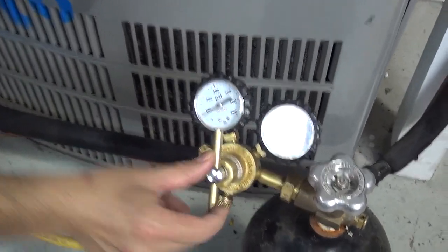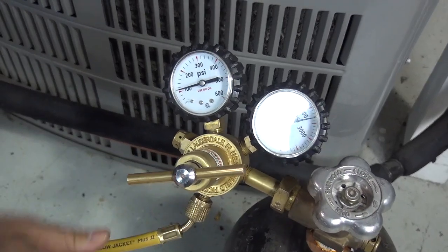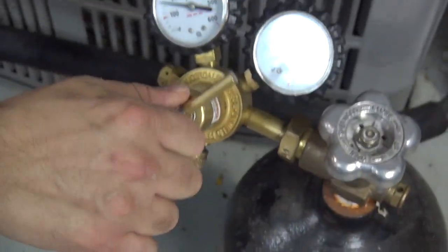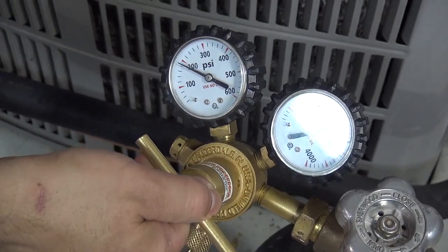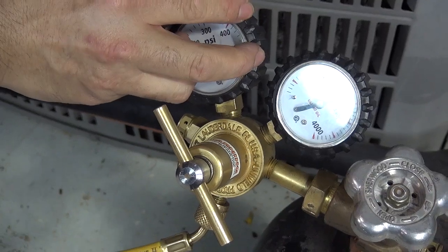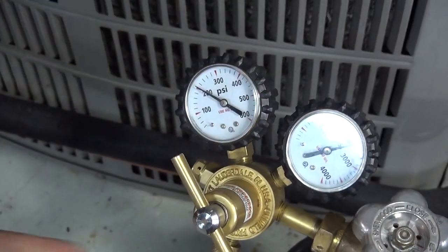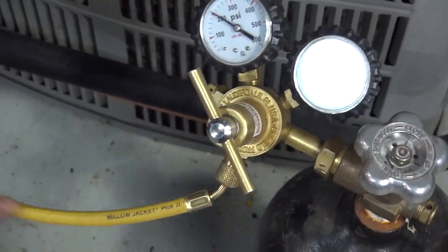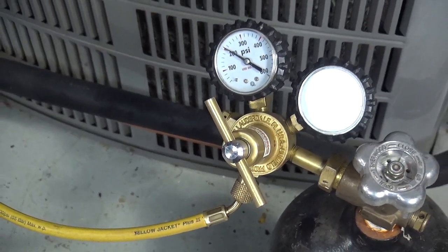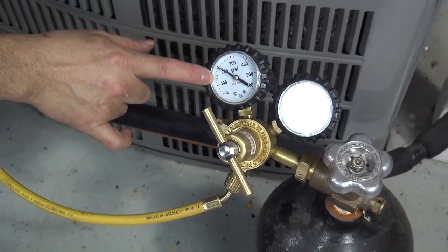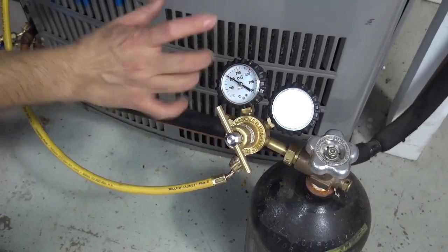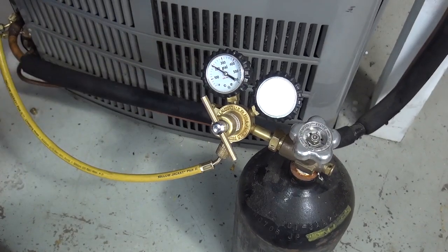See that? The pressure starts to increase. All right. Let's bring it to somewhere around 200 and no more than that. That's the pressure that you put into the gauge. Now, when this pressure comes out of here and goes to the gauges, we're only going to set the pressure on the condenser up to 150 psig, no more than that. You can leave the regulator at 200, no more. You can go less if you want to, but 200 is good.